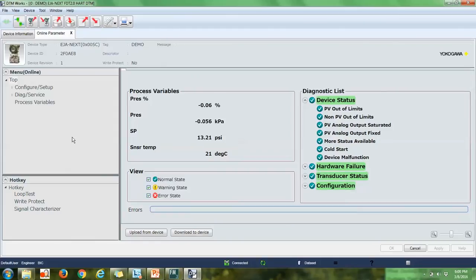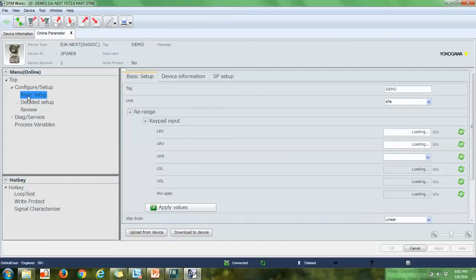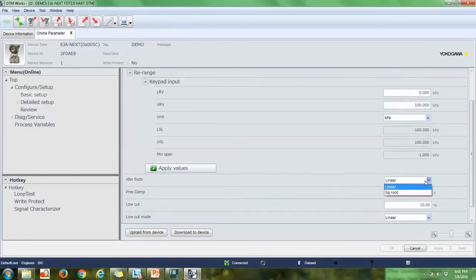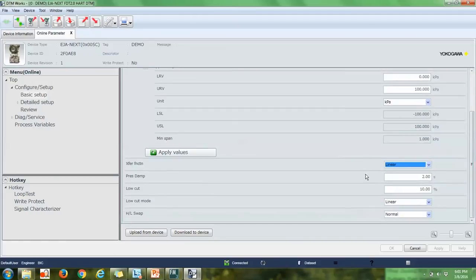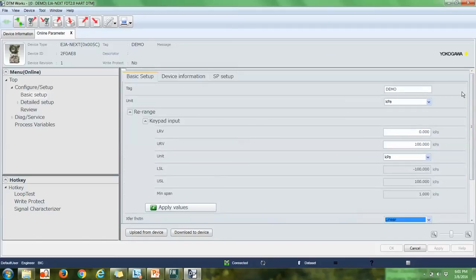So again, we want to trim our transmitter. That's our ultimate goal after doing our calibration that we found was out of tolerance. So if we go to Configure, Basic Setup, I'll just show you this first. This is a good place to do all the basic things that need to be done with a pressure transmitter. If you want to set up your tag, rerange your transmitter, set up your units, set up your transfer function, maybe to square root if you have a DP flow application, or your damping, all your typical parameters are set here.